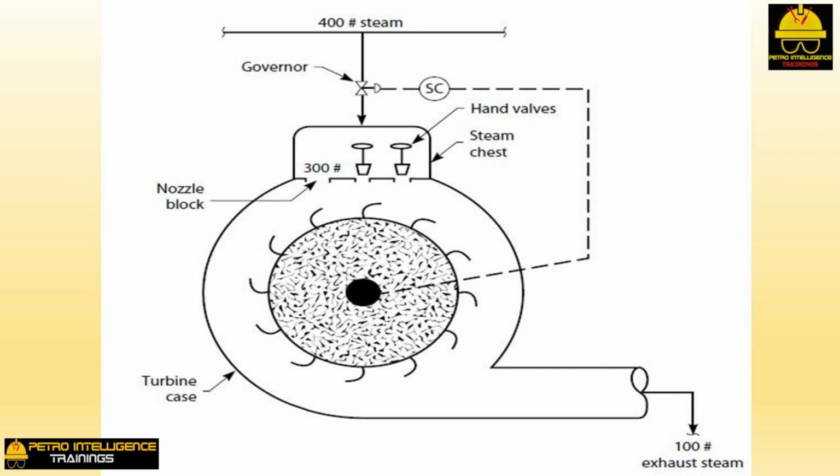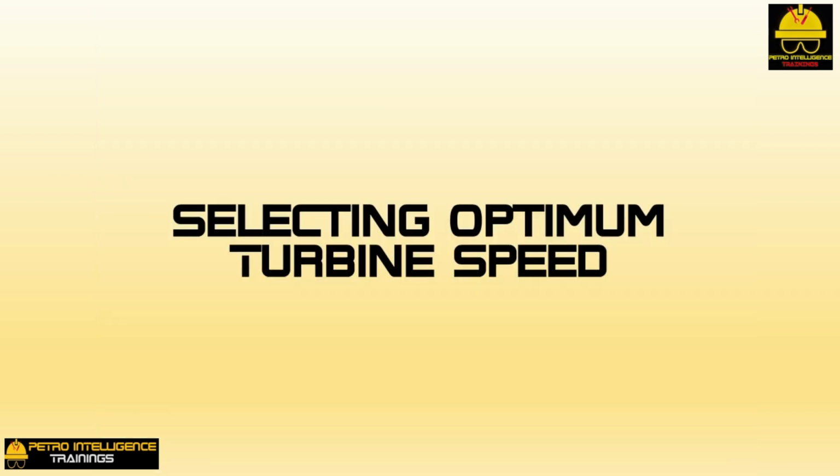Do not pinch on the horsepower valves. They must be left completely open or firmly closed. Leaving them in a partially open position will badly damage the valve seats by erosion, reduce the efficiency of the turbine, and make it impossible to close the valves in the future.